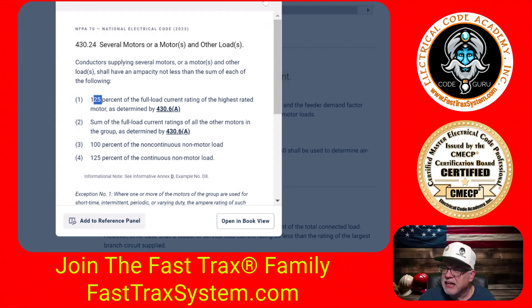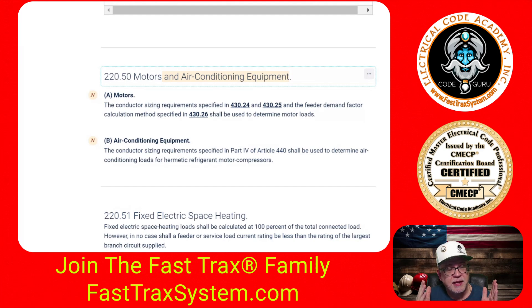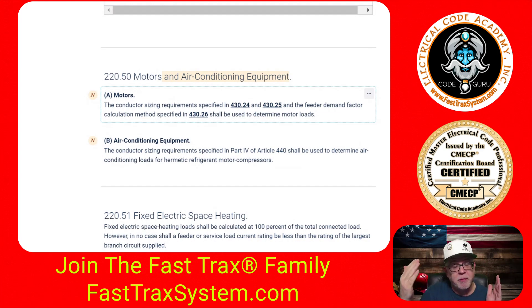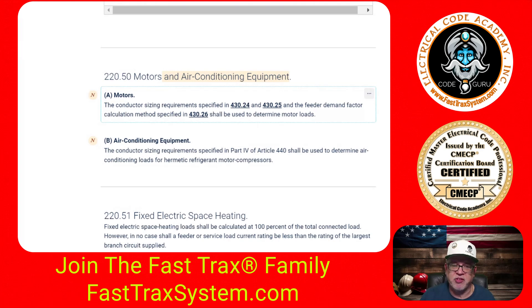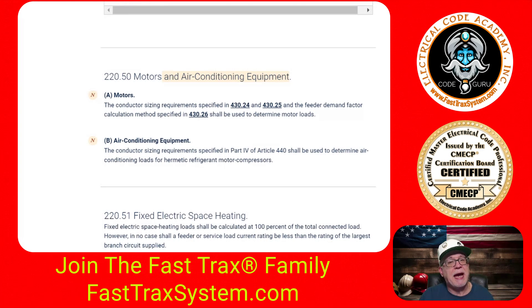This is where it comes from. It can get very confusing when you're doing the standard method, because you don't do this in the optional method. Under the standard method, when somebody says take the largest motor and get 25% of it — we're getting it from 220.50 and following the rules. Since we have multiple motors in the building, we're hunting for the largest one, taking 25% of that value, and adding it to our standard load calculation. We're accounting for just that additional 25%.